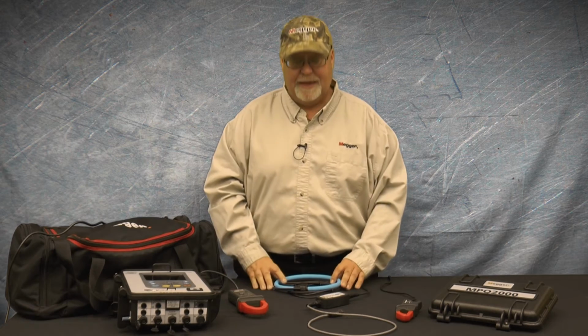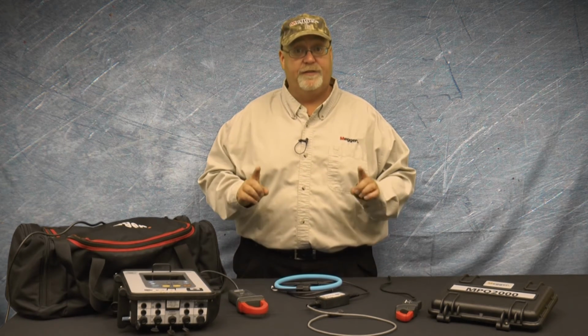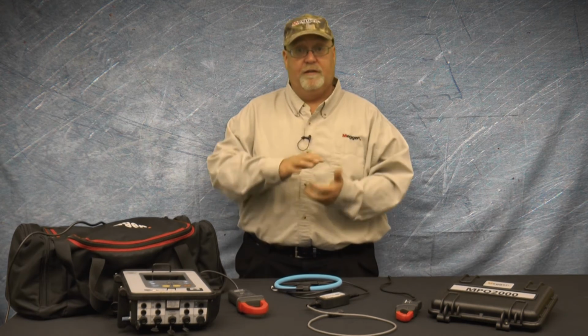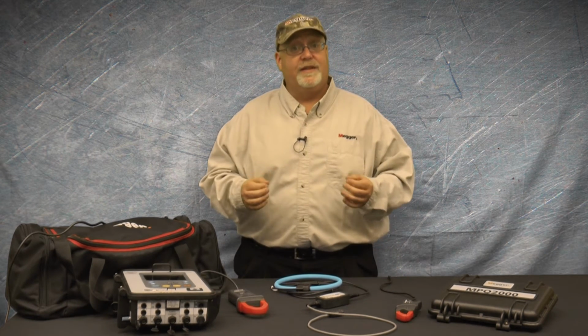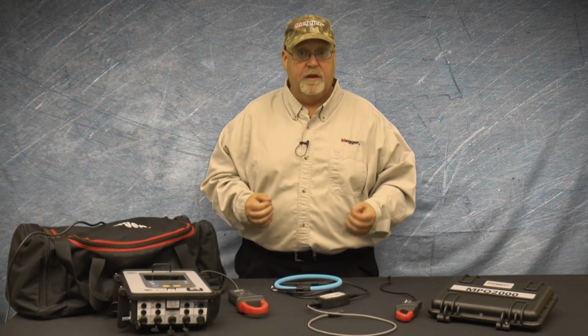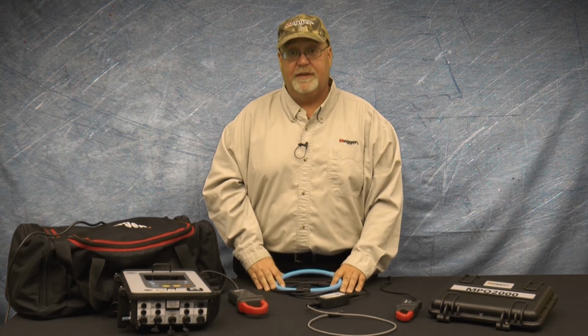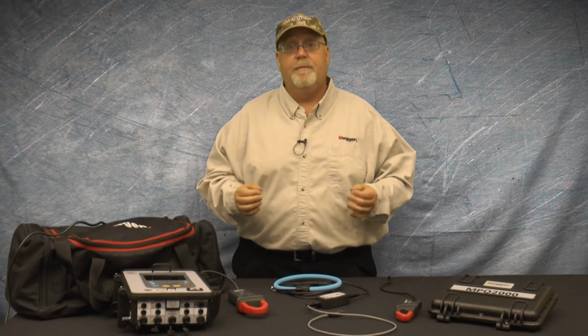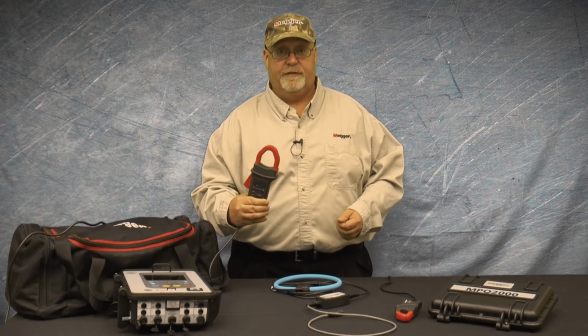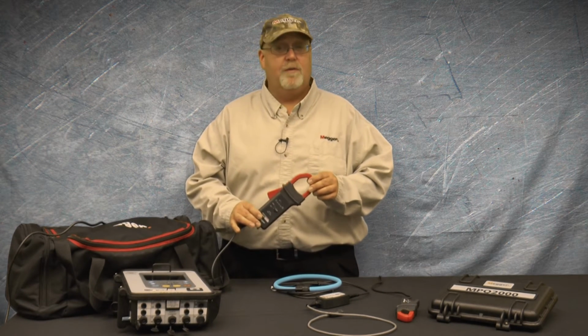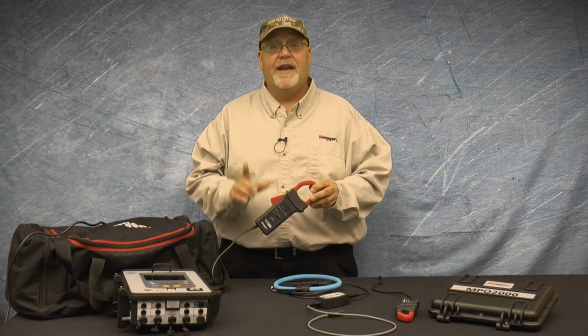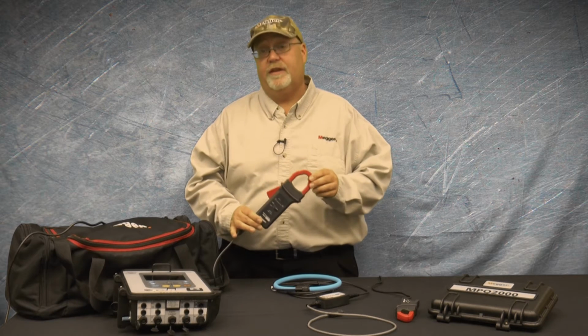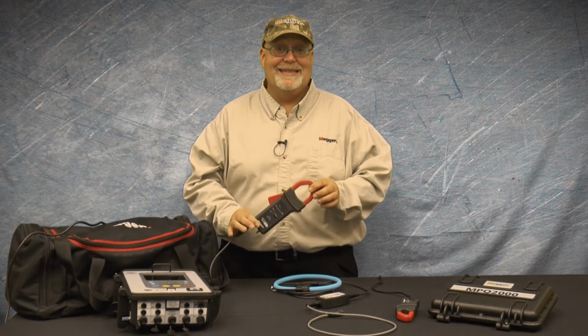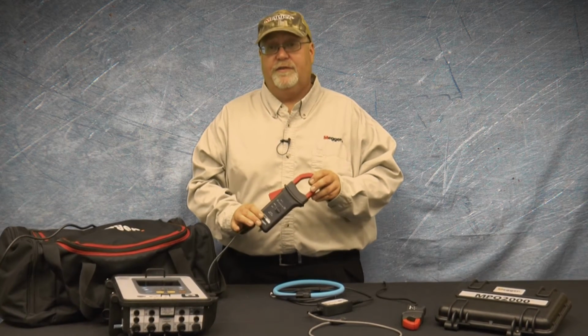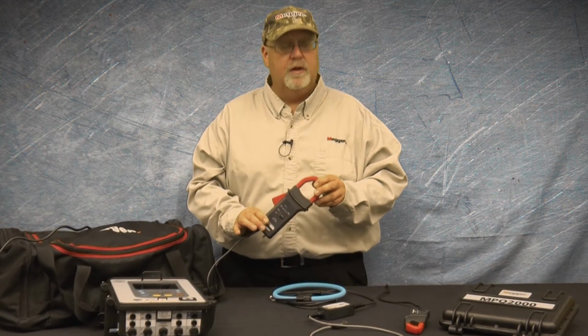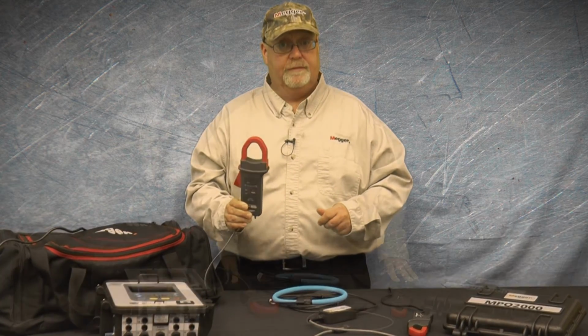Both the split core CT and the flexible Rogowski coil only measure AC current. It is the change in the alternating field that induces the current in them. Now, DC, direct current, does not have an alternating field. So neither the split core nor the flexible CT can measure DC current. If you need to measure DC current, you'll need to use a Hall-effect CT. The Hall-effect sensor varies its output in response to the magnetic field. This does not have to be a changing magnetic field, so the Hall-effect sensor can measure both DC current and AC current. Hall-effect sensors do have circuitry in them, so they do require power, so Hall-effect sensors are battery operated.